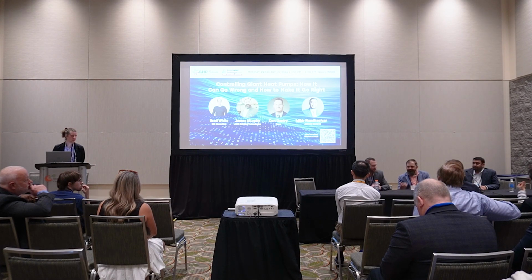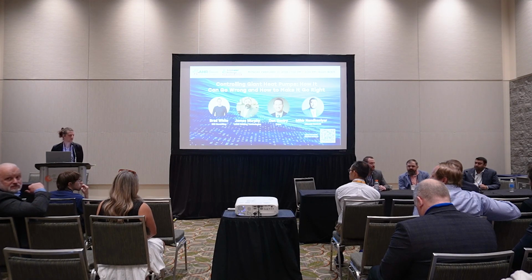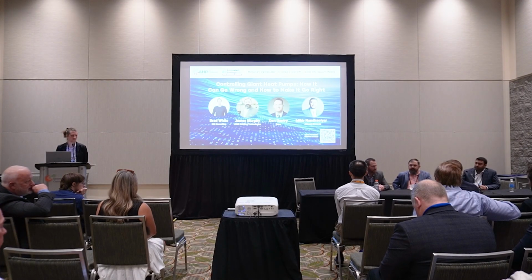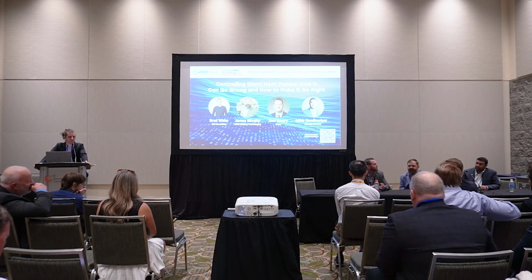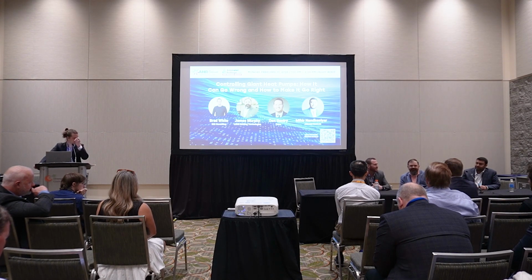I think that depends on the customer, because we see some that are just measuring temperature and proving flow, and that's fine, while others will have BTU meters and flow meters all set up, with more advanced controls and multiple pieces of equipment for staging. Heating turndown is one of the biggest conversations we have: what's the minimum load of the unit, what's the minimum load of the system, and making sure we're picking the right technology, like we talked about, positive displacement versus centrifugals. You don't want to surge a centrifugal chiller and have the customer asking what's going on. Whereas a screw compressor would probably be more robust in some of those applications. You guys hit it really well, actually.